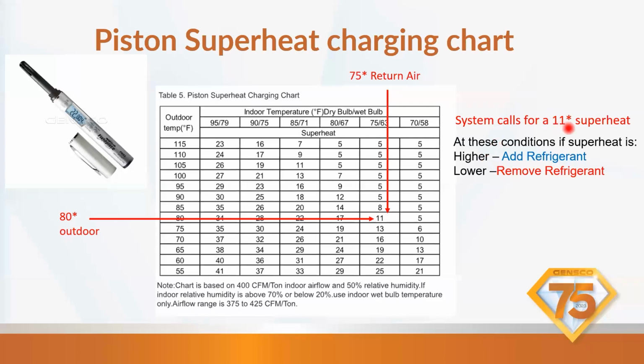If we have lower than 11 degrees superheat, if we have 7 to 8, we're going to remove refrigerant, and that's going to raise the superheat. So that's a good slide there, because that kind of looks backwards, right? But adding refrigerant will lower the superheat, so we want to remove it.